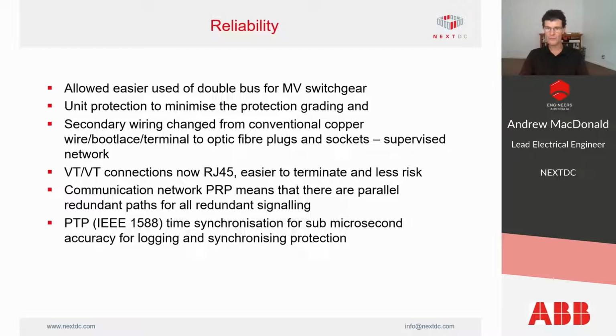The CT and VT connections are now RJ45, so they're easier to terminate and there's less risk of getting the polarity wrong. No risk, it's fixed. And the communication network over PRP means that there are parallel redundant paths for all of the signalling, which makes our signalling wiring redundant as well, which goes to improve the reliability. We're also using PTP for time synchronization, which provides sub-microsecond accuracy for logging and synchronizing the protection.